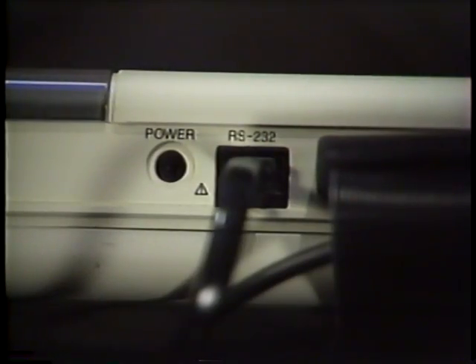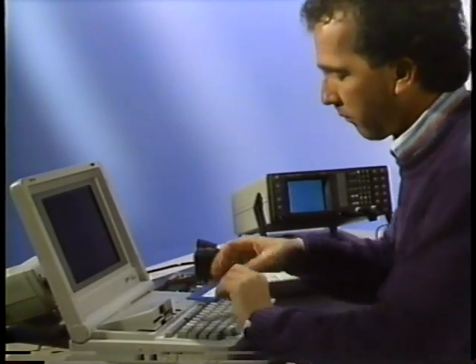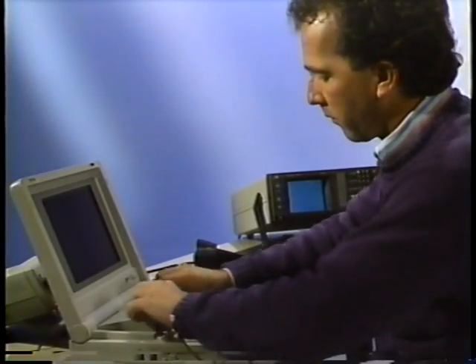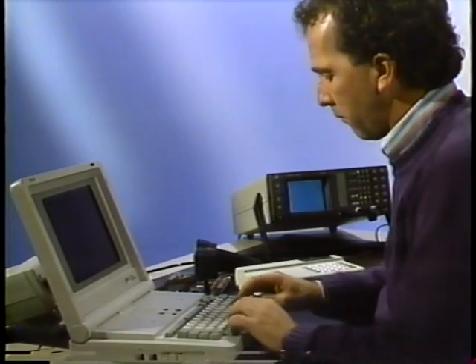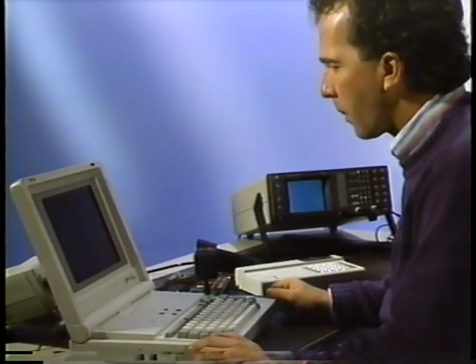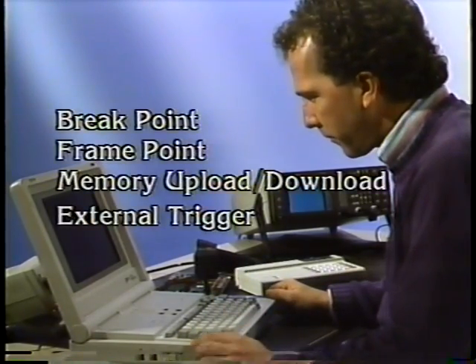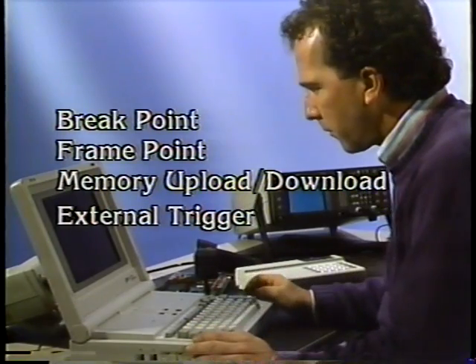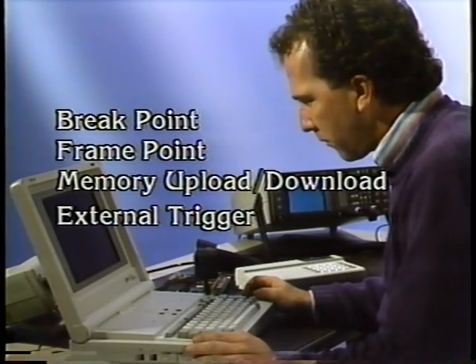The Fluke 90 tester can be operated remotely by connecting it to a host PC or terminal through its RS-232C interface. In this mode, all commands are issued at the remote terminal. Some additional test routines are available in this mode which cannot be generated locally at the Fluke 90 keyboard.